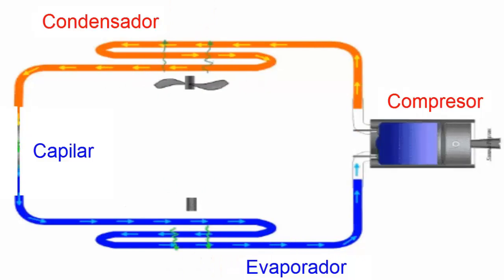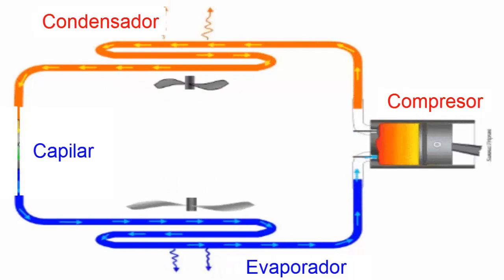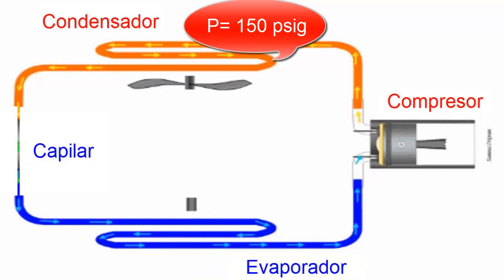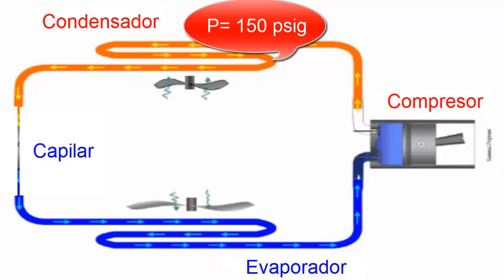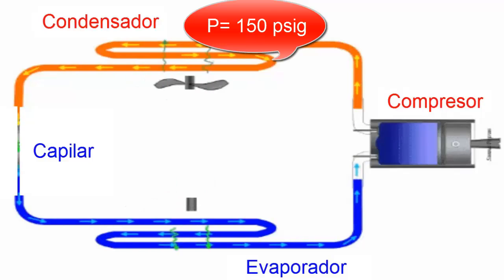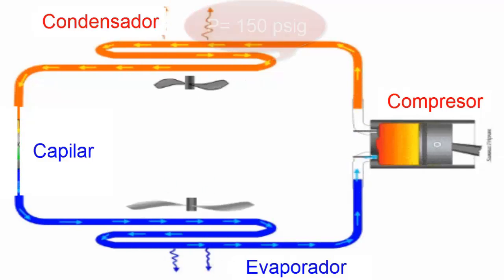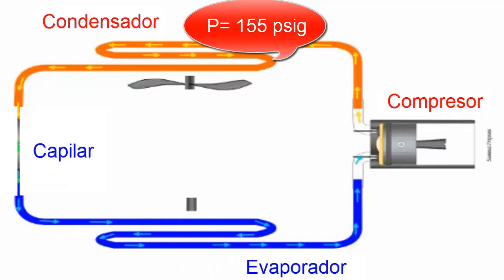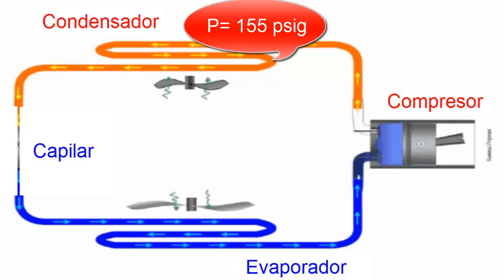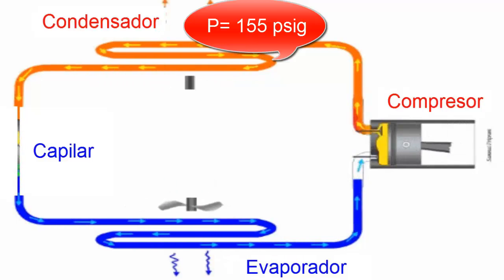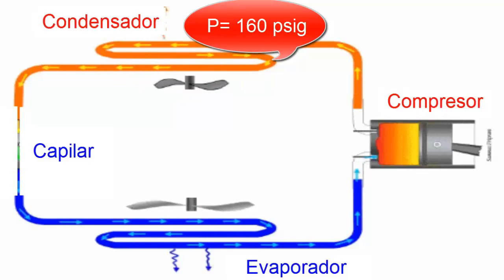3. Despite the obstruction, the compressor continues to suction and discharge refrigerant into the condenser. The condenser, initially at 150 pounds per square inch, starts receiving refrigerant at high pressure. However, due to the obstruction, the refrigerant begins to concentrate in this area, causing an increase in high pressure.